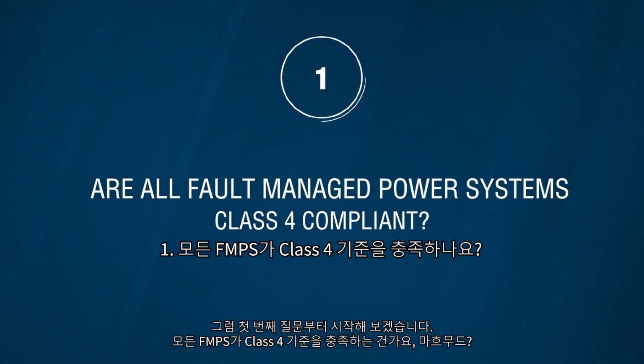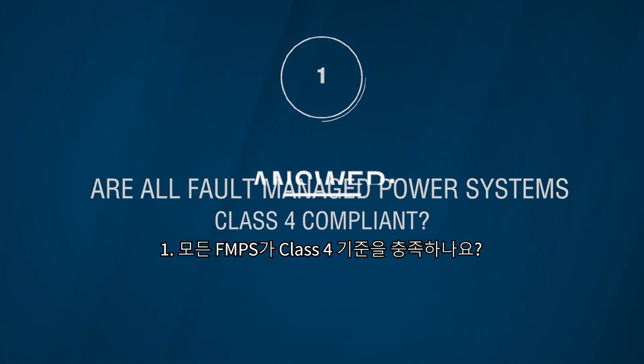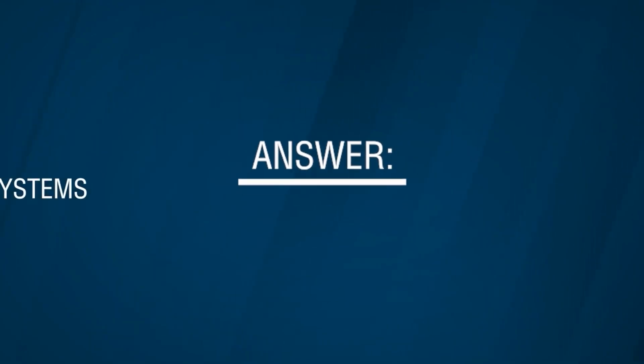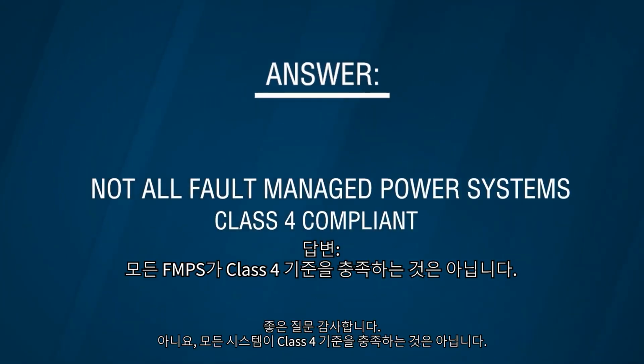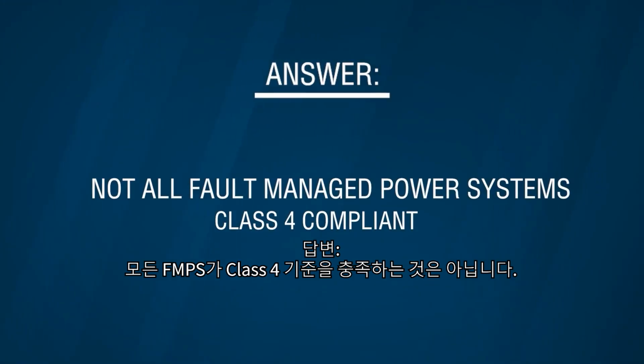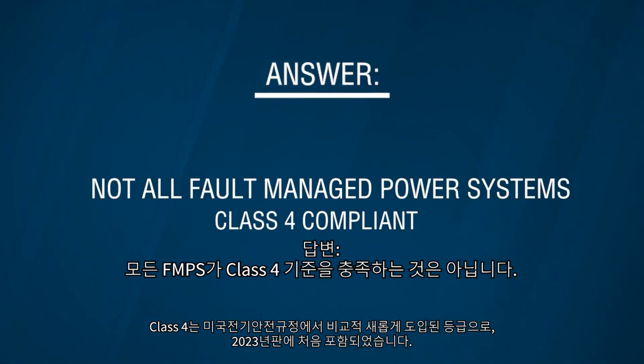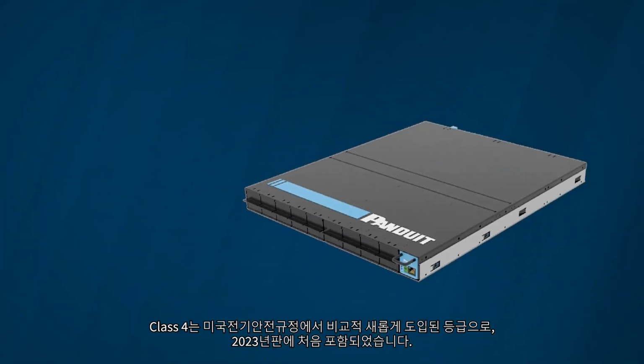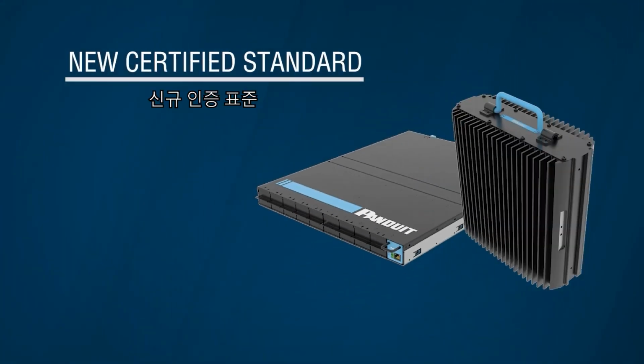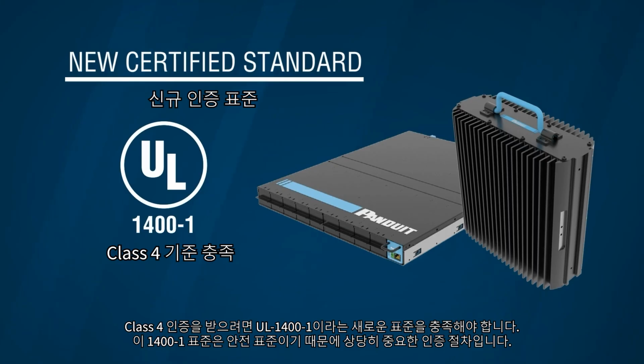Are all fault managed power systems Class 4 compliant, Mahmoud? Thanks for that question. No, they're not. And Class 4 is relatively new in the National Electrical Code. It just came out for the 2023 version. And you have to be certified to a new standard called UL 1400-1 to get to Class 4 compliance, which is somewhat of a big deal because that 1400-1 standard is a safety standard.